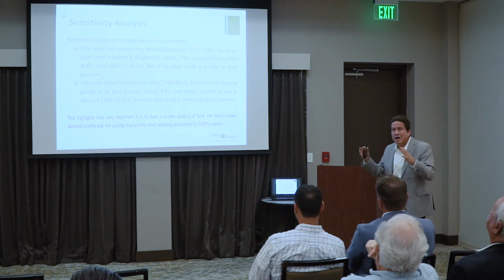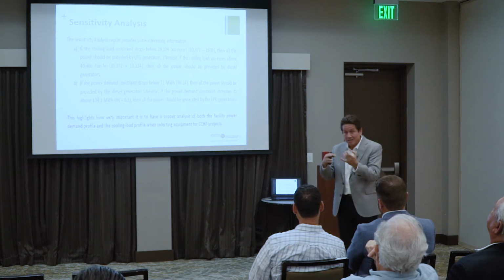So you understand, you have to do a proper engineering analysis. You have to analyze the loads. What is a proper cooling load? And you know, some engineers, we don't want to get embarrassed if it's not cooling, so we overestimate, or we put extra - instead of 10 or 15%, we might put 20%, right?